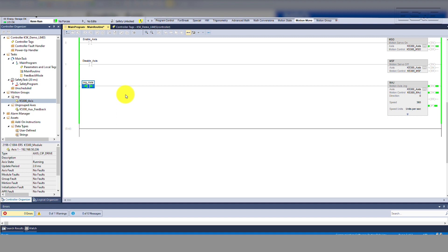As you can see, when the rung is true the enable bit is true. This instruction executed successfully, so you can see that the done bit is also true. You can also see that the in-process bit is true — this means that the instruction is currently active and running the move profile on the target axis. The IP bit will stay on until another instruction is executed that stops this one.